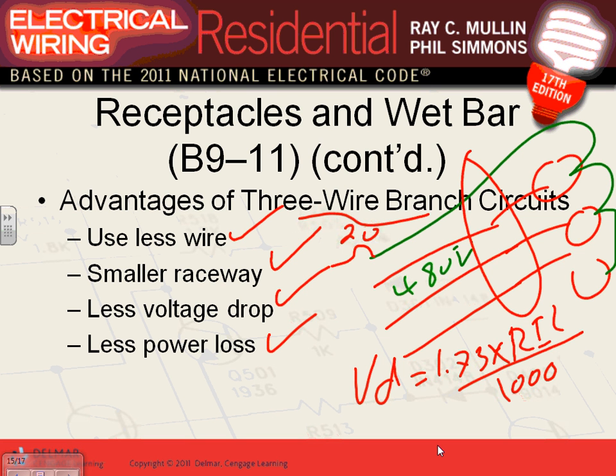If you do the math on it, guys, you will see that the voltage drop will be much lower with a multi-wire branch circuit. Then, what's the alternative? The alternative is to take this, and this. So here's 1, here's 2, here's 3, and do the calculation for each one of them. If you do the voltage drop for each one of the circuits, versus doing them all together as a multi-wire branch circuit, you're going to find this one will give you a substantial amount less voltage drop than if you do a single voltage drop, hot and neutral with all.